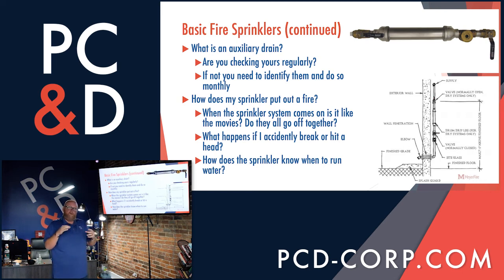We also, as systems age, they will start to leak. A certain amount of leaks is normal, it's to be expected. But you may have some leaks start to take place around some of your gaskets where the two pieces of pipe come together. You may even start to have some very slight pinholes that start to come in your system, and they'll just leak a little bit of air over time. Leaks in dry systems are normal. I won't say that they're acceptable. We would love to have a totally sealed system, but the realities are in our buildings today, as old as a lot of these nursing homes are, they simply leak. That's the point of your air compressor.